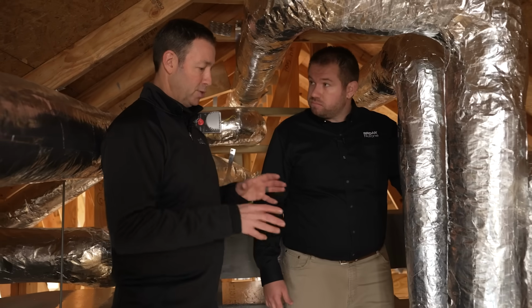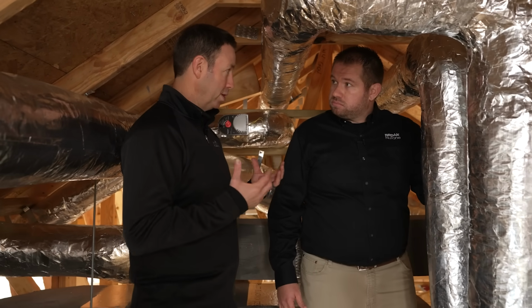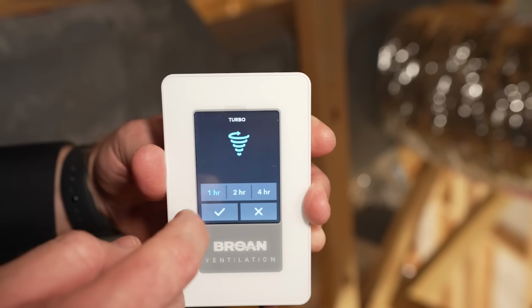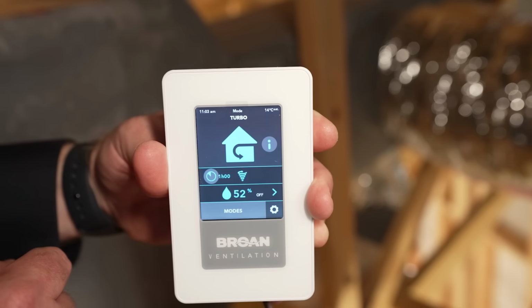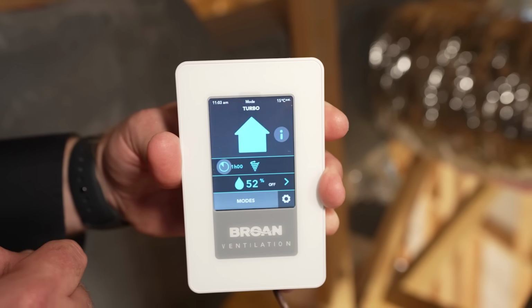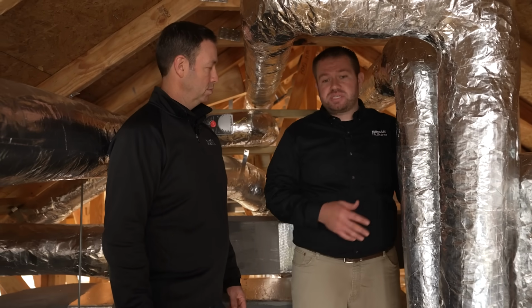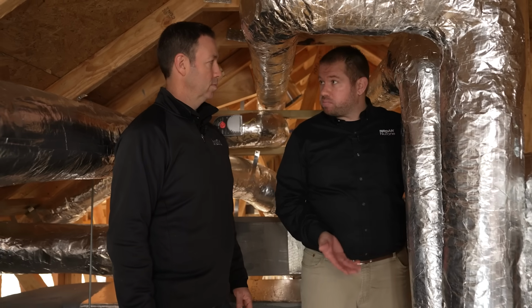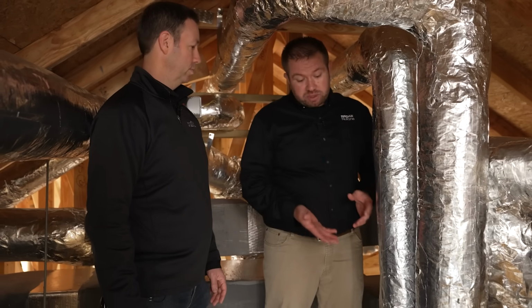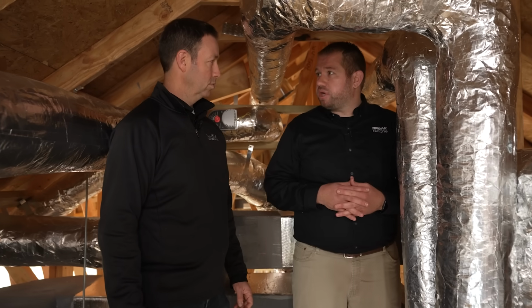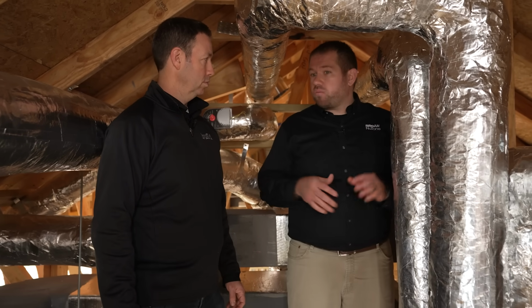Now this particular unit, talk to me about what normal runtime and what boost mode means. With a house like this, around 3,200 square feet, if we do some of the ASHRAE calculations, we're looking at about 70 CFM as what we'd want from a continuous standpoint. From a max speed standpoint, we have a full range in this platform—units that top out at 110 CFM, units that go up to 160 CFM. This particular unit being the B150, we'd expect that to top out around 150 CFM, which will be more than adequate for what Luke has here.